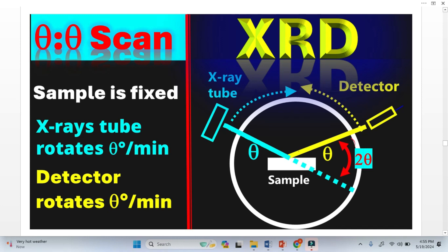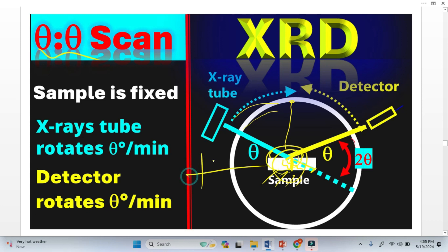Similarly, if you look at the theta-theta setup, the sample is fixed. At lower angle — both the incident and reflected angles are the same — there is more probability for the X-ray to scatter. Once we rotate the X-ray tube and it reaches a higher angle, look at the difference in thickness the X-ray must pass through. There is a huge difference. This is why at lower angle the intensity is higher, and it decreases with increasing 2-theta angle.